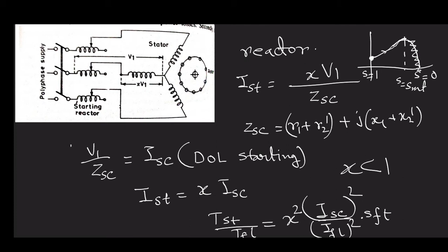But on this side, once it reaches a small slip value, it offers a high value of rotor effective impedance, reducing the current requirement. The same thing happens in case of auto transformer starting. All these formulas will become applicable to auto transformer starting as well. Only here, due to auto transformer action, a slight difference will take place in the current equation, and let me show you.